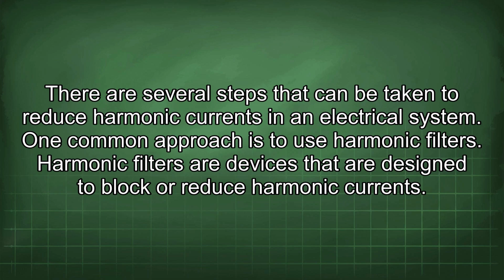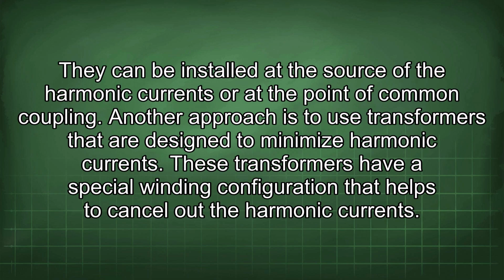There are several steps that can be taken to reduce harmonic currents in an electrical system. One common approach is to use harmonic filters. Harmonic filters are devices that are designed to block or reduce harmonic currents. They can be installed at the source of the harmonic currents or at the point of common coupling. Another approach is to use transformers that are designed to minimize harmonic currents. These transformers have a special winding configuration that helps to cancel out the harmonic currents.